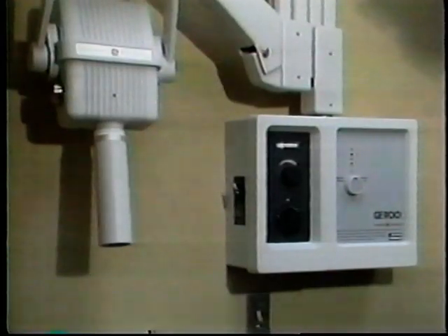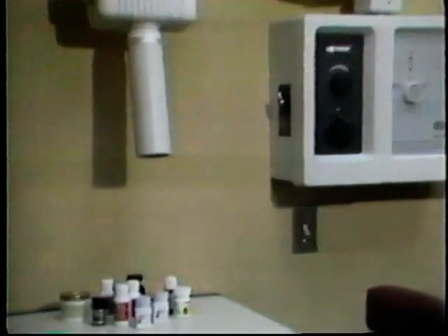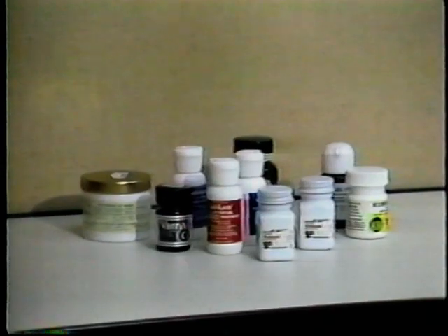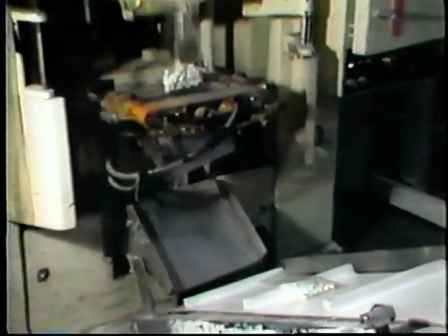Oil removal filtration is needed in many different applications, such as dental and medical, pharmaceutical, food processing, and paint spraying, just to name a few. These filters can be very efficient. One of these units, equipped with a pre-filter, can remove as much as 99.9% of the oil and particles down to approximately 0.3 micrometers. Let's see how it's made and how it works.